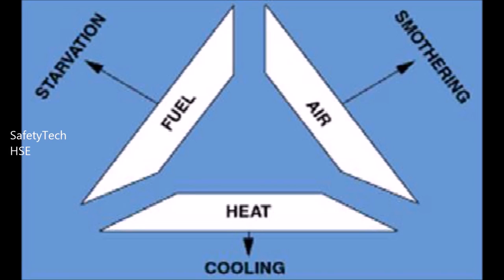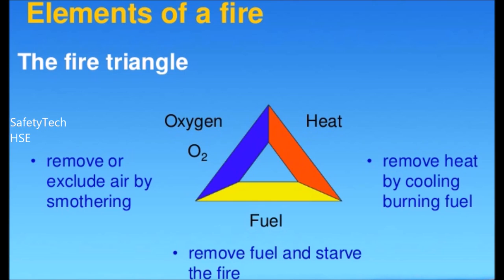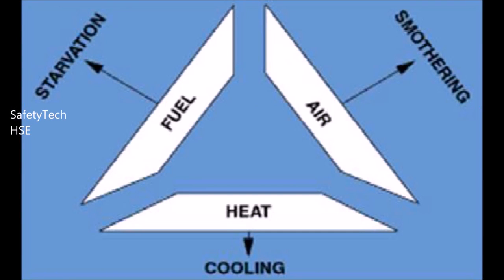1. Starvation: the extinction of fire by starvation is applied in three ways. First, by removing combustible material from the neighborhood of the fire. Examples of this are the drainage of fuel from burning oil tanks, the working out of cargo at a ship fire, the cutting of trenches in peat, heath and forest fires, the demolition of buildings to create a fire stop, and counter burning in forest fires.